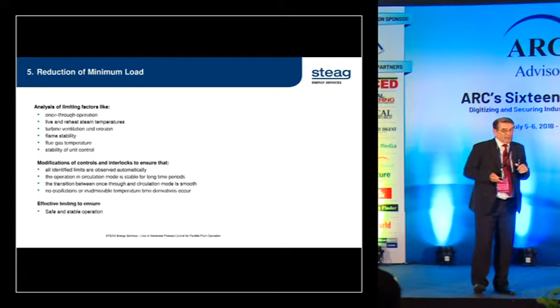So, if we now look at the next slide, we see here the potential. What is the potential of minimizing the load? So, for instance, when you look at the second unit, we minimized the load from almost 37% to 20%, and in other cases, we minimized the minimum load even to 10%. We ensure the boiler can operate with only one mill in a stable way. On the other hand, we have information from the operators of the lignite power plants that such a big reduction was not possible in some power plants, and they put in a lot of effort to reduce the minimum load by only 10%. So these figures are especially from our power plants, and we achieved a really good result in minimizing the load.